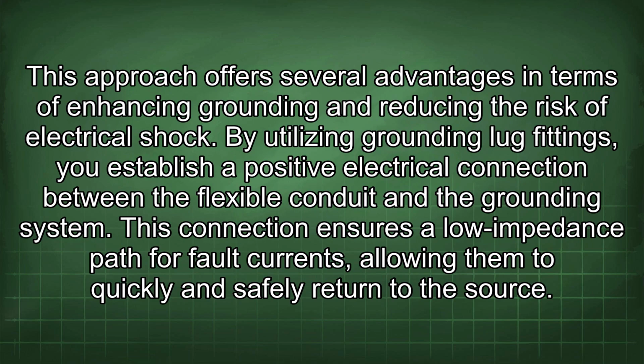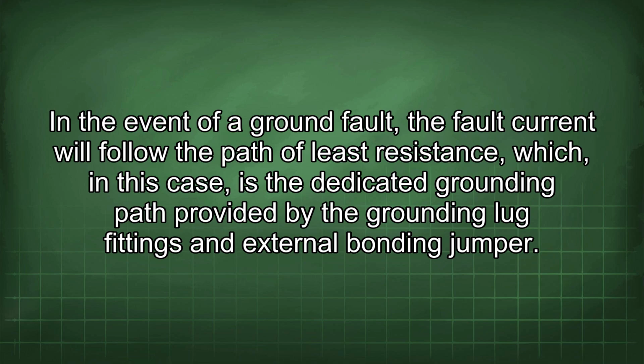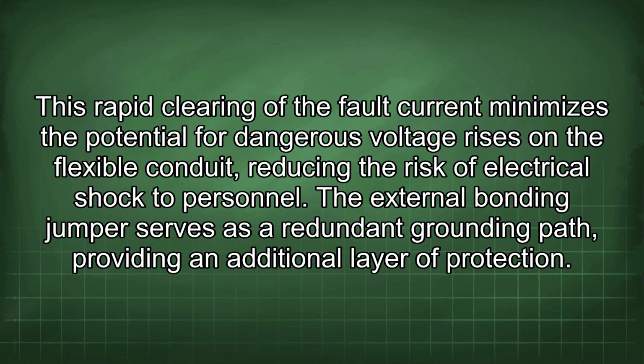This approach offers several advantages in terms of enhancing grounding and reducing the risk of electrical shock. By utilizing grounding lug fittings, you establish a positive electrical connection between the flexible conduit and the grounding system. This connection ensures a low impedance path for fault currents, allowing them to quickly and safely return to the source. In the event of a ground fault, the fault current will follow the path of least resistance, which, in this case, is the dedicated grounding path provided by the grounding lug fittings and external bonding jumper. This rapid clearing of the fault current minimizes the potential for dangerous voltage rises in the flexible conduit, reducing the risk of electrical shock to personnel.